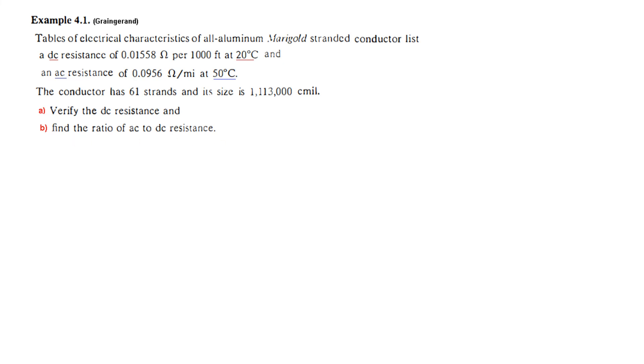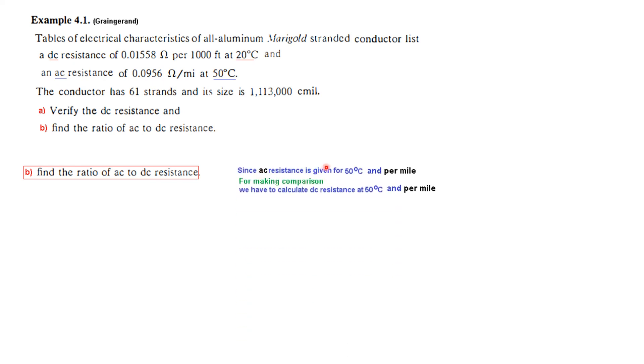Now we calculate the ratio of AC to DC resistance. The AC resistance is given at 50 degrees centigrade and per mile. For comparison, we need to calculate the DC resistance at 50 degrees centigrade and per mile. We first apply the temperature correction formula to convert DC resistance from 20 degrees to 50 degrees.